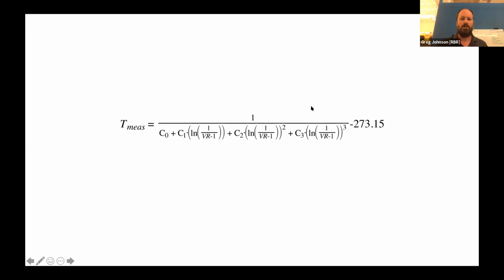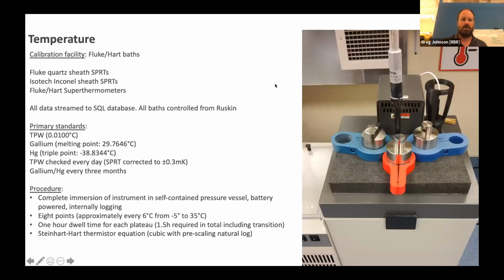So how do we do that in terms of the instruments that we have? We have these Fluke-Hart baths, which, as I said, are very stable, but they're not very accurate. We don't actually care about the accuracy of the bath at all, because we're not going to calibrate at exactly 6-degree steps. We're going to calibrate at approximately 6-degree steps, but we're going to measure the temperature very accurately using a standard platinum resistance thermometer, SPRT. I didn't actually pull out an SPRT to show you while I was in the lab. It was something I meant to do, but I didn't.